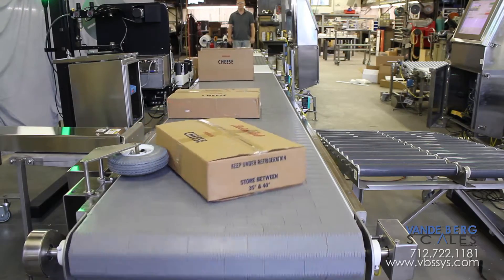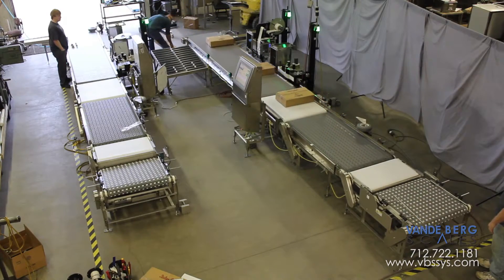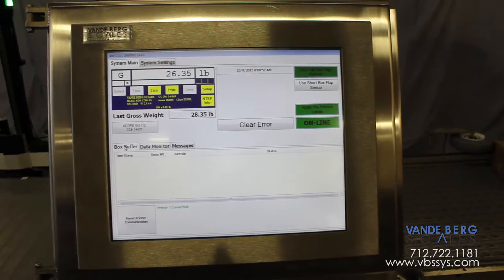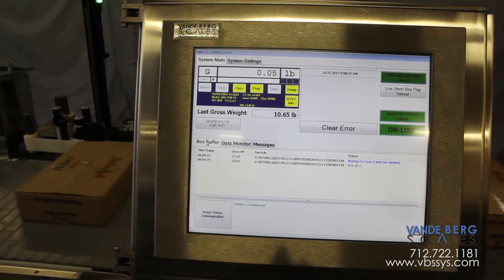This particular customer required a second retractable box turning wheel to rotate boxes that are too wide for the downline conveyor. All of the above functions are controlled and monitored with our scale data system controller. It records all weights, scanned images, divert activations, and other vital data in an SQL database.